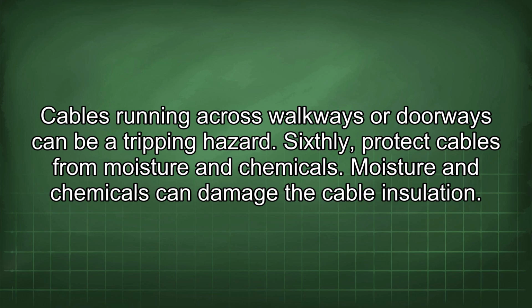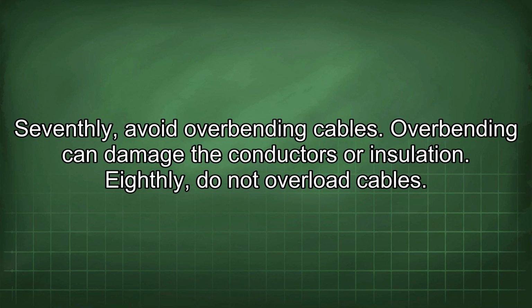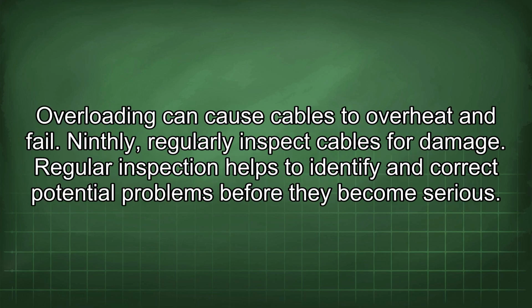Sixthly, protect cables from moisture and chemicals. Moisture and chemicals can damage the cable insulation. Seventhly, avoid overbending cables. Overbending can damage the conductors or insulation. Eighthly, do not overload cables. Overloading can cause cables to overheat and fail.